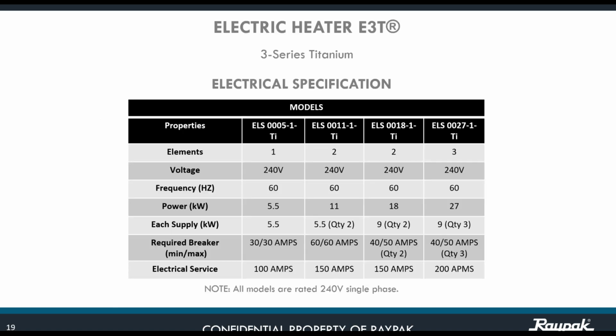On the electrical side, let's see this. There are a number of elements per kilowatt capacity for the units. For the 5.5, we have one element. For the 11, we have two. For the 18, we have two elements. And for the 27, we have 3 elements. Voltage for all of them is 240. No less than that, or the unit might not work properly. The power for them, as you see, is 5.5 kilowatts, 11 kilowatts, 18, and 27.